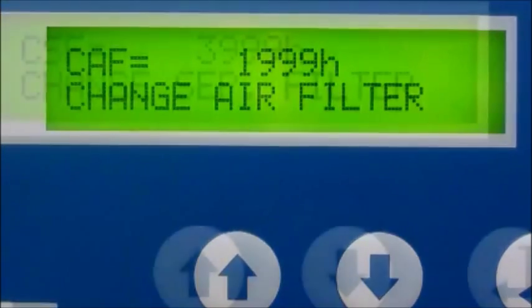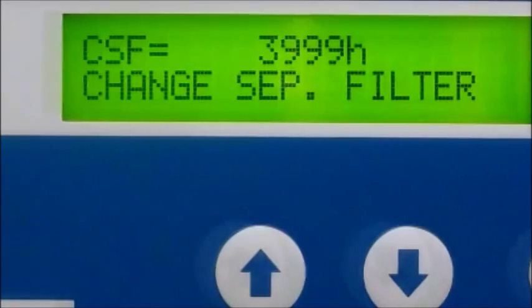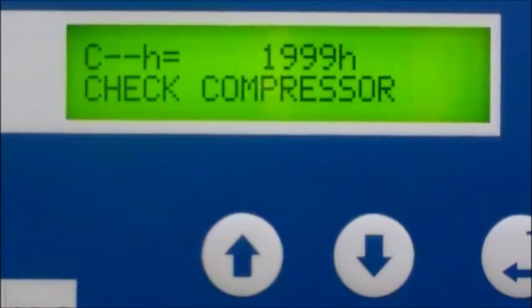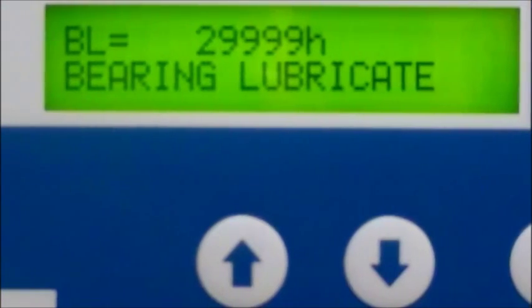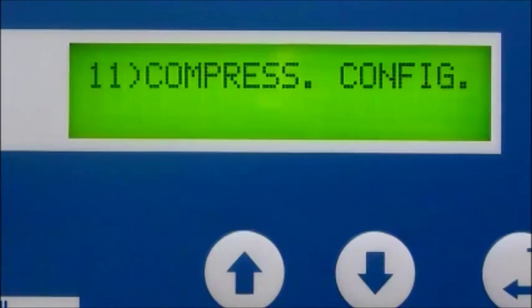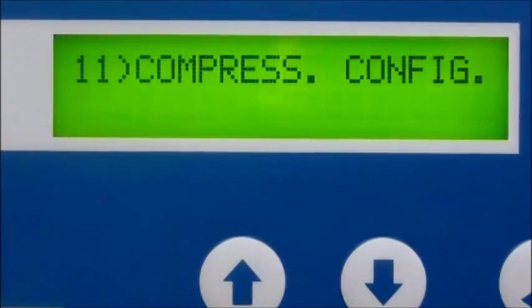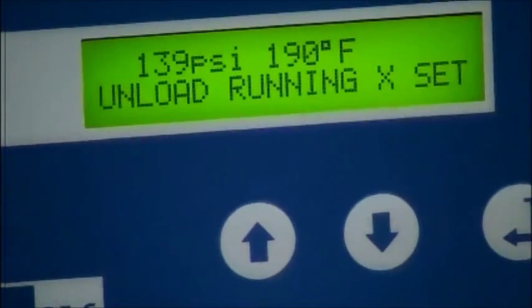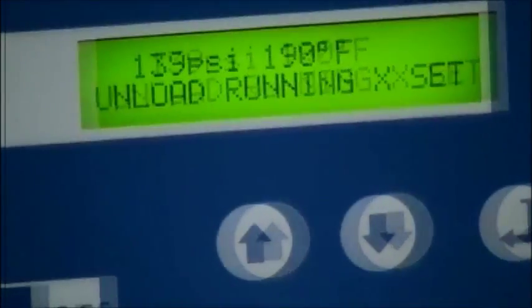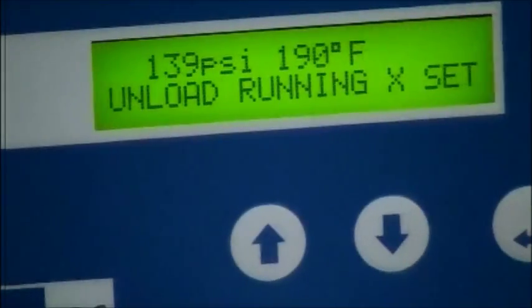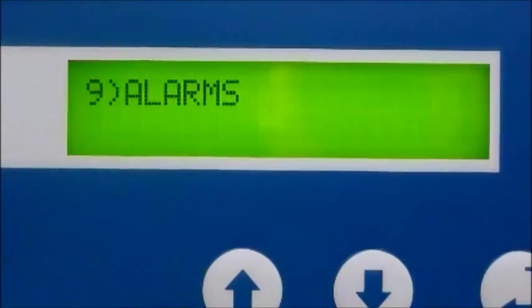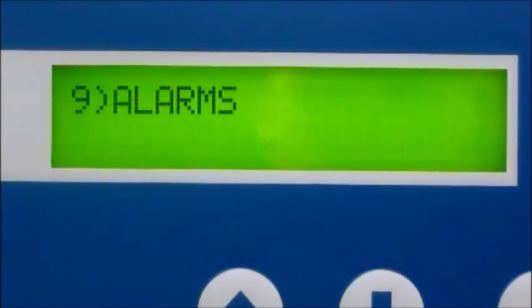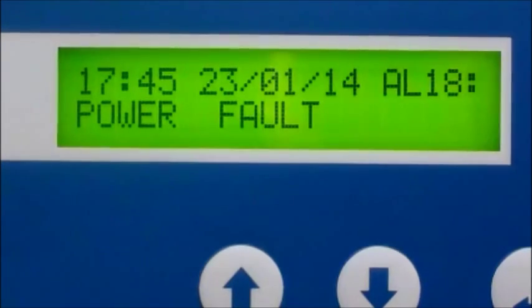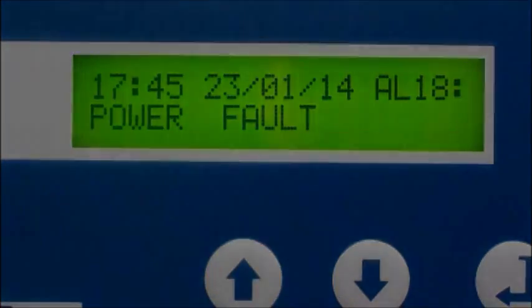Wrapping up the PLC segment of this video, I will briefly touch on the preventive maintenance alerts. The PLC will alert you when the compressor requires routine maintenance such as oil change, replacing the filter, mechanical checks, and bearing lube. This is driven by the PLC built-in hour meter. Another helpful feature is the load, unload hours log, which proves helpful when fine-tuning your compressor through programmable features previously mentioned. In case you are not familiar with the term load, unload, load means the pump is in the pressure mode, and unload means the pump is in a freewheel mode, making no pressure. A real time saver is the detailed fault history page containing a date, time, and frequency of any compressor fault. This feature quickly directs you to the source of the problem.